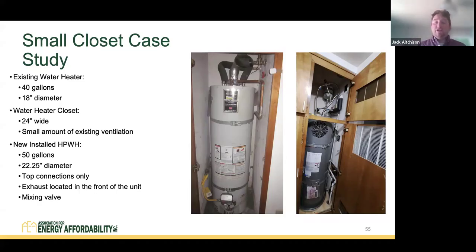We also included a mixing valve. What a mixing valve allows us to do is store water at a hotter temperature, which effectively increases the storage volume. If you can imagine, the water heater is storing water at 130 degrees. You're using water at your tap at 105 degrees. Cold water is mixing with that hot water to deliver 105 at the tap. And that really is a way to expand or increase the effective storage volume without actually increasing the footprint.